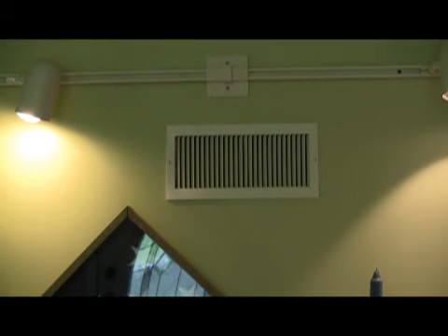This is the high wall cold air return — probably the most important part of any forced air heating and cooling system. If you don't have a cold air return in each bedroom, in the air conditioning mode you will not be able to make those bedrooms comfortable, because this is where the humidity and heat is drawn back to the furnace to be removed in the summertime. Also, do not block this register with furniture, as that would cause the air distribution system not to function as designed.